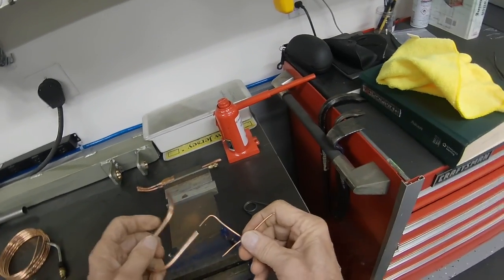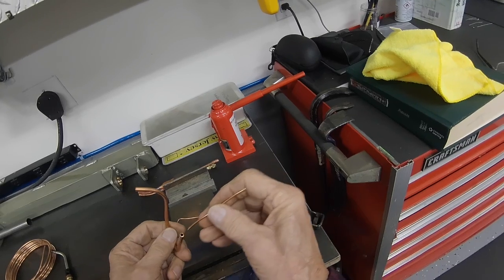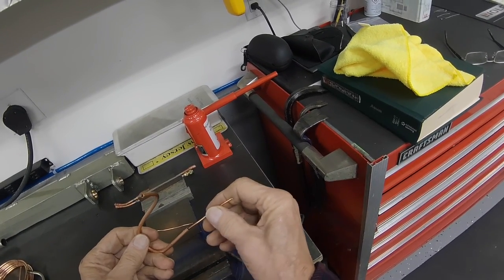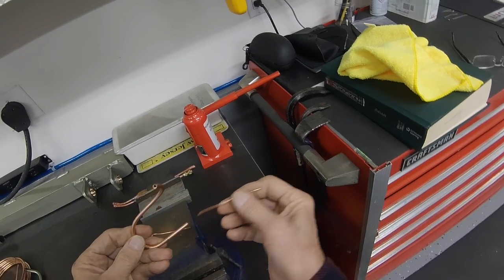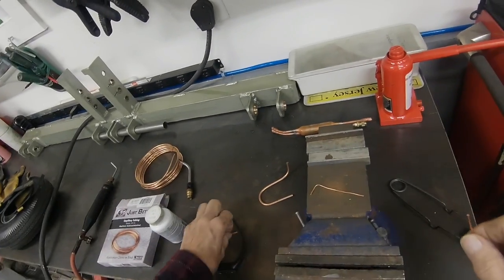This is a piece of 3-16ths tubing. You could use 3-16ths tubing but there's still a lot of play and a lot of gap. There's a lot of opportunity for the solder to flow in there and clog up the line.